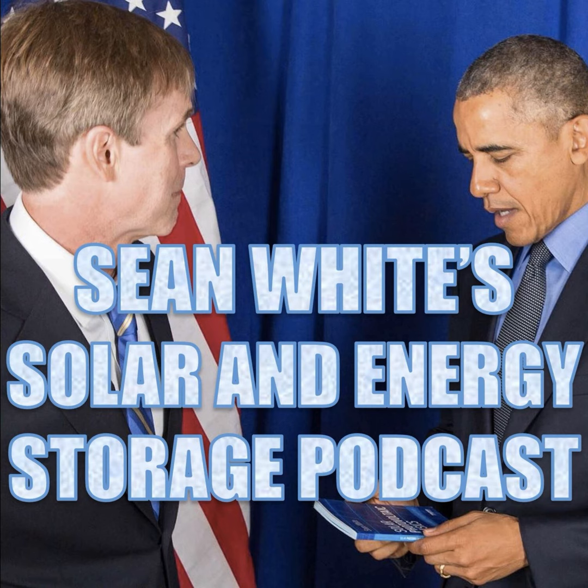So for instance, if you're going to have one of these energy storage systems that we've been looking at and your live parts are hidden and you're not supposed to do maintenance on them, then the output of that energy storage system that includes an off switch can be up to 600 volts. So usually what we're looking at for dwelling units, 600 volts. So the exception is the rule. And you will notice that many of our energy storage systems go over 100 volts on the output, but some of them stay down to 48 volts, and then you can do maintenance on these conductors.